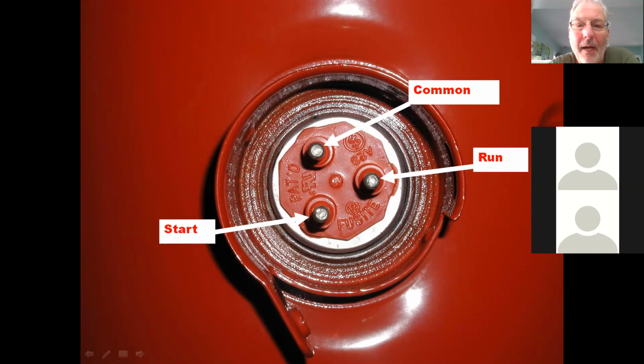Here we go. Is it okay to pull leads off the compressor to check windings if the unit has a charge? I've heard not to do that. Oh, you mean for fear of losing the charge? As long as the power's off, it shouldn't be an issue. I think it's done all the time. The one thing you don't want to do, and I cover this a little bit later, is you never ever want to put power to a compressor in a vacuum.